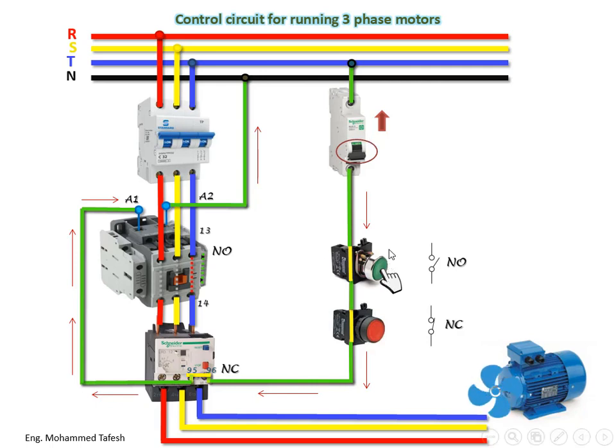If I take my hand off the push button ON, the motor turns off. Why? The push button ON changes from normally closed back to normally open, so the circuit opens and the electrical signal is cut off from the contactor coil. The main contact positions open for all three phases and return to their normal state.